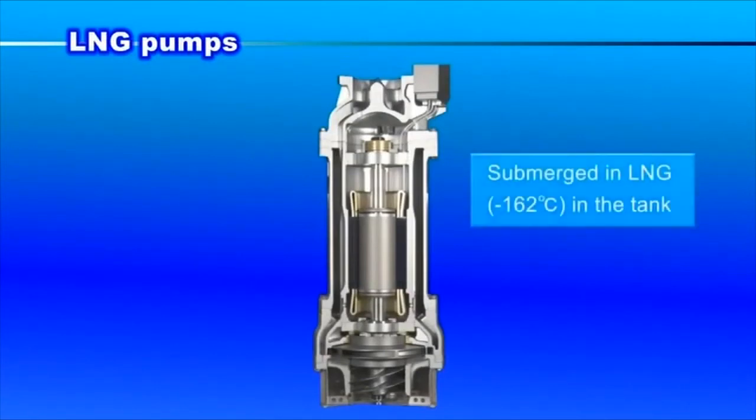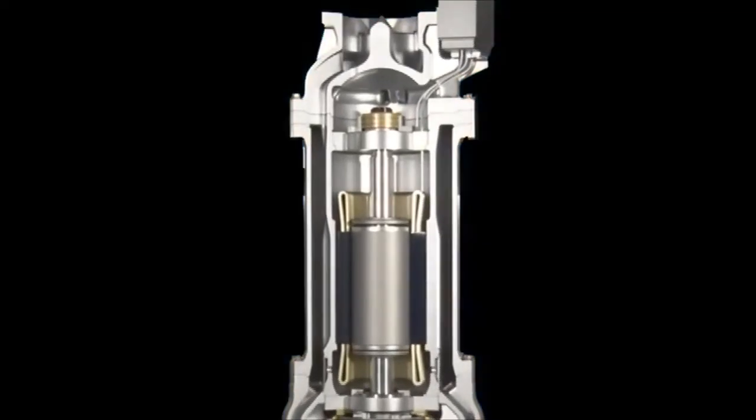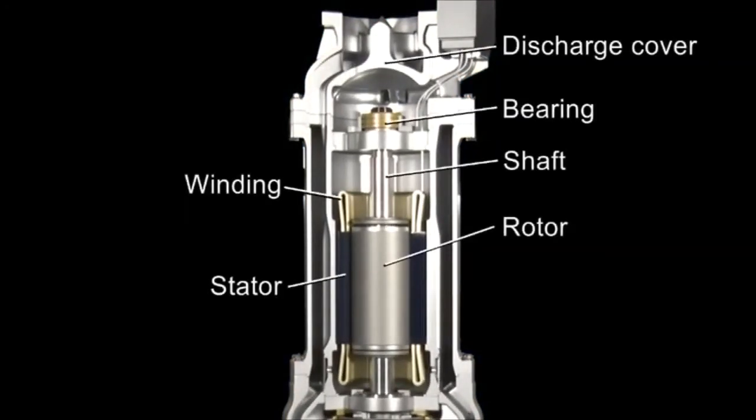The pump for LNG cargo handling is a submerged pump that can be found at the bottom of an LNG tank. The motor is made of a special cryogenic metal because it is also submerged in the LNG liquid with the boiling point at minus 162 degrees Celsius.